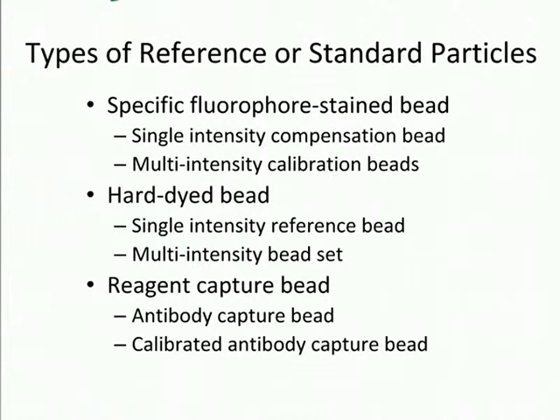A practical solution is to cross-calibrate hard-dyed beads against specific fluorochrome beads and make your own MESF value assignments. These assignments will only be accurate on the instrument where the cross-calibration was performed — not valid for a different instrument with different filters or laser power. With this in mind, cross-calibrated hard-dyed beads are a very convenient reagent. Both specific fluorophore beads and hard-dyed beads are available as single beads or as multi-intensity sets. The third type is a reagent capture bead, exemplified by antibody capture beads used as compensation standards, with different amounts of capture reagent allowing an alternative calibration approach.